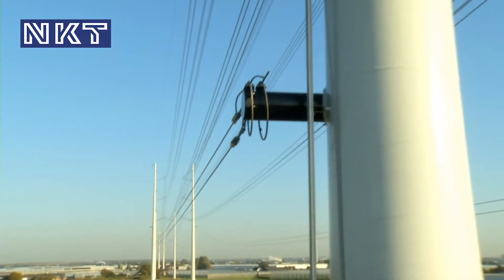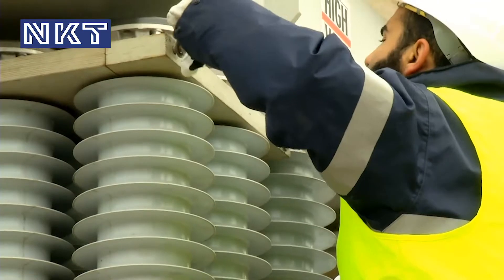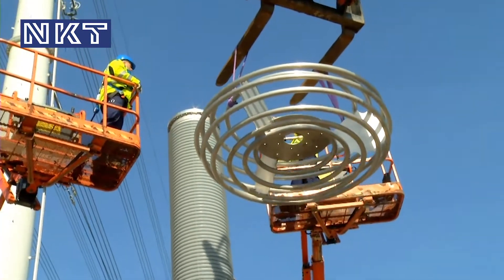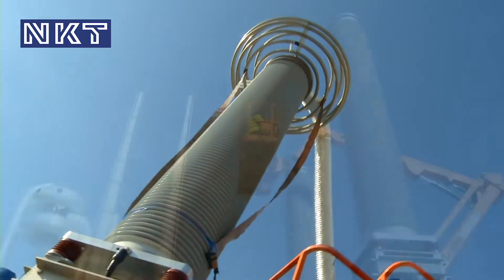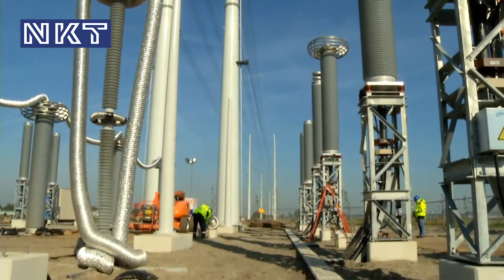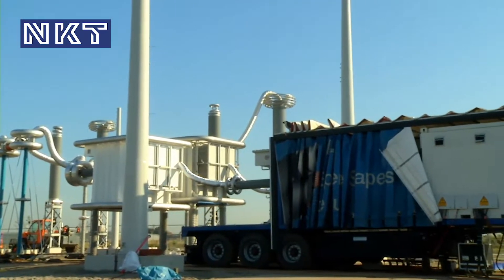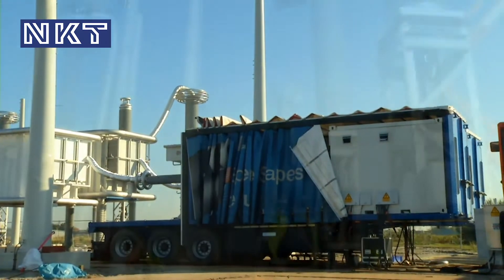To take advantage of this newly installed 380kV cable system of almost 11km in length, it is necessary beforehand to perform a high voltage test. This test is realized by the interconnection of four resonance test systems — two each in series and then connected in parallel.